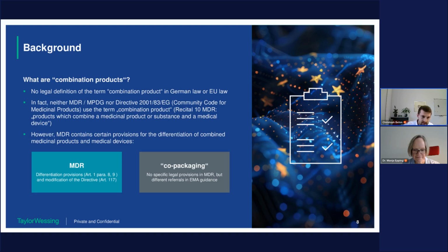For these combinations, certain guidelines of the EMA, the European Medicines Agency, come into play. For example, the EMA guideline stipulates that for co-packaged products, the product information should follow certain requirements. And also, as another example, moreover, the use of the medicinal product with the device should be demonstrated to be safe and effective. Therefore, compatibility between device and drug product must be demonstrated. As you may know, in this case, the famous interaction studies should be performed.